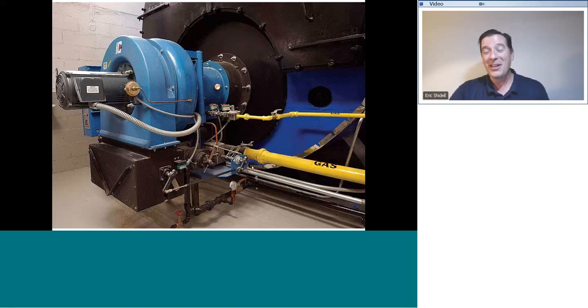Here's how this whole thing works. On a demand for heat, number one, the fan starts. This modulating motor will stroke this damper to go fully open. When it opens, the blower will be generating enough draft to close a pressure switch. That pressure switch will close, indicating that we have the ability to move air through the system at full fire. Cool. Then the damper will go full closed. The pressure switch will open, sending a signal saying we will open the pressure switch when there is no flow of combustion air. Next, the pilot burner will fire.